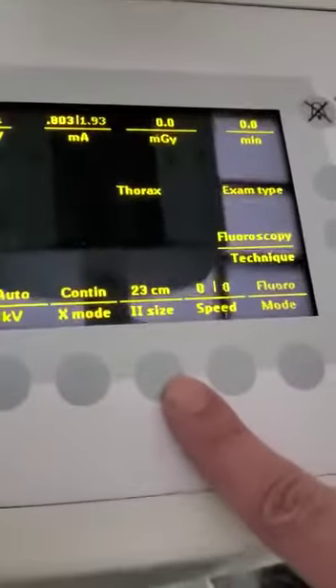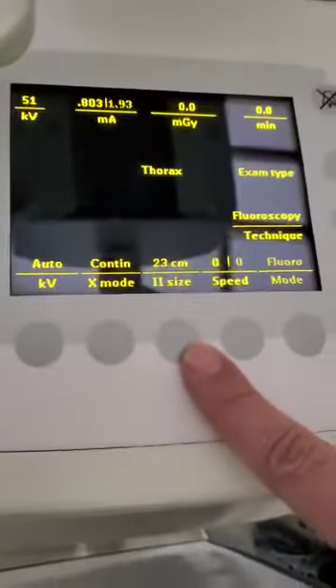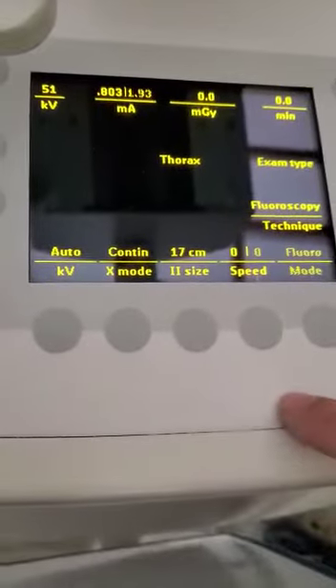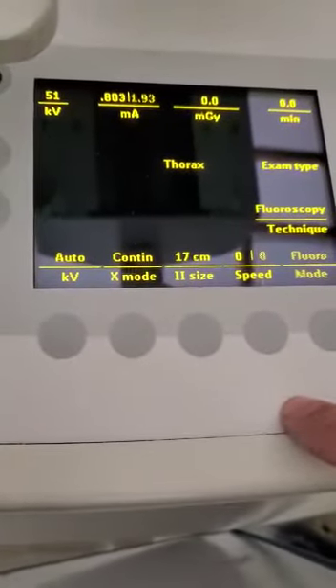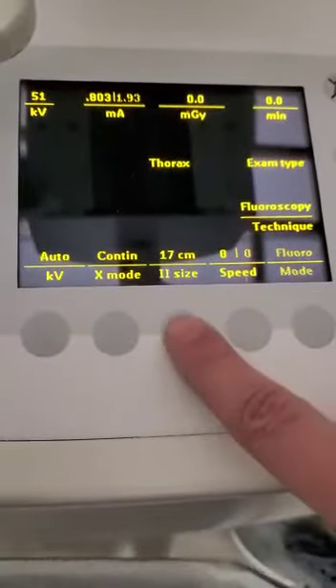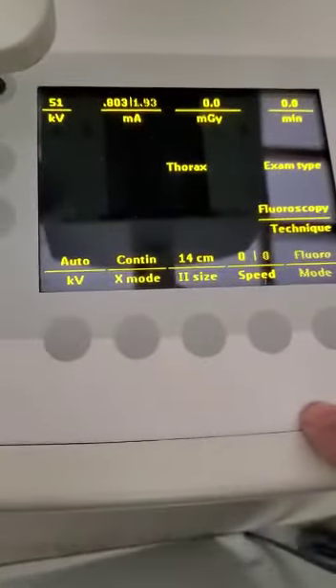And that reminds me, we did not cover magnification, which is done right here. The one thing we skipped was magging. 23 centimeters is your 9-inch setting. So the image you see is at 23 centimeters. If you want to mag down to 6 inches, that is done right there, which is at 17 centimeters, and then down to 4. And then back to 23.